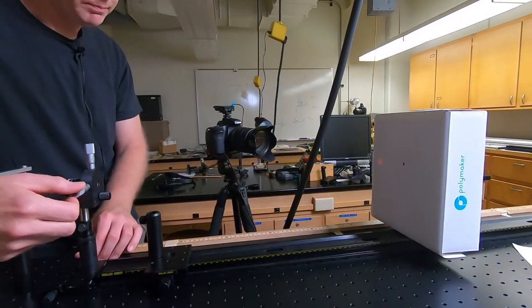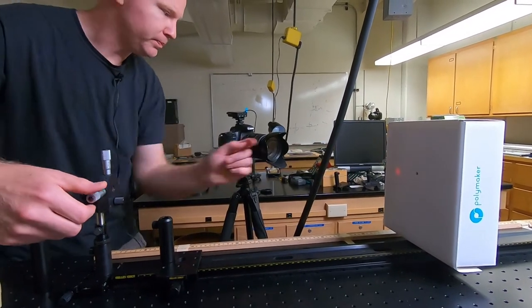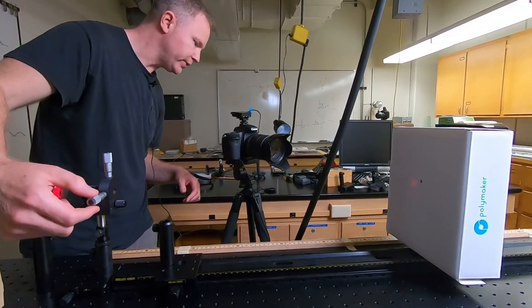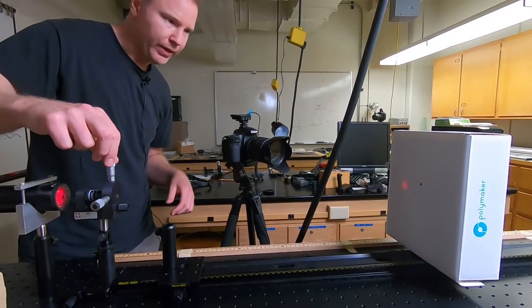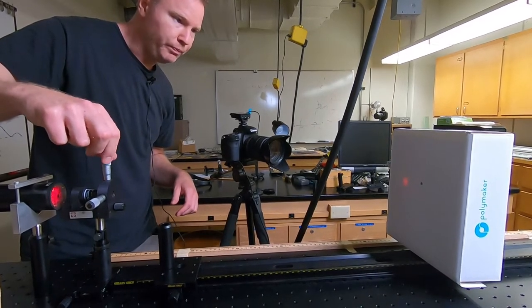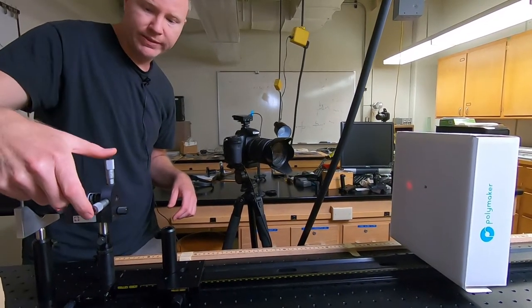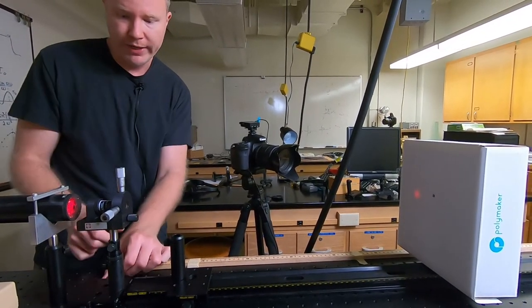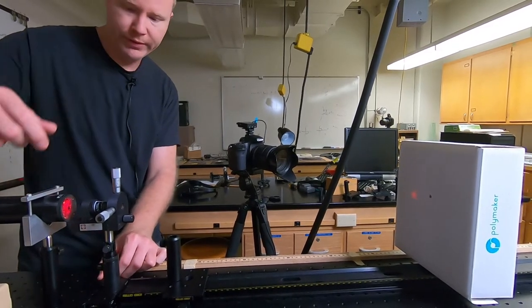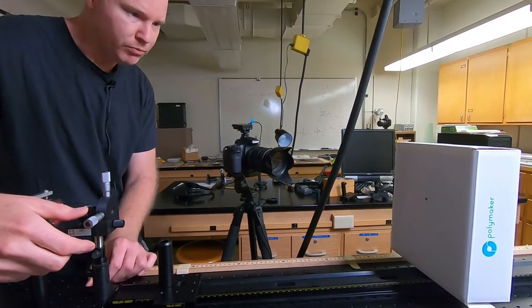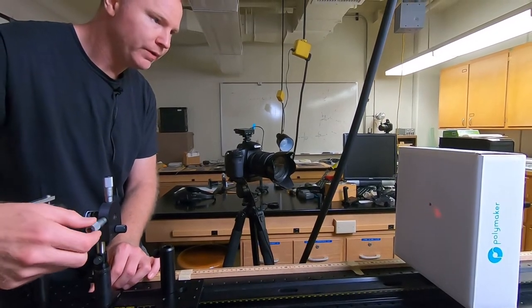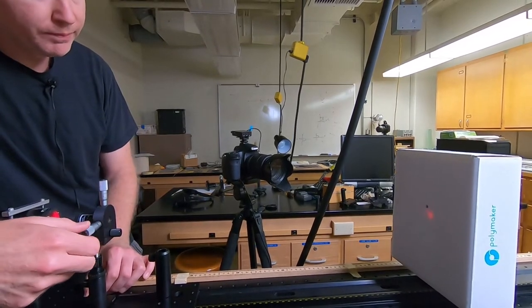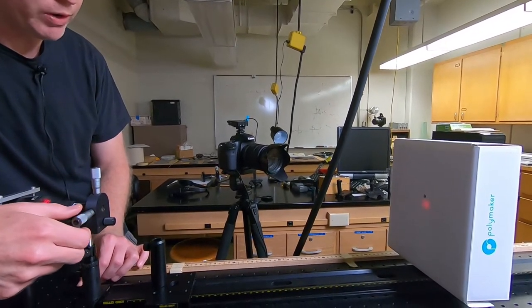The X and Y adjustment, I want to adjust it to make this spot as bright as possible. On the zoom in camera you can sort of see in the center where it's bright, and the Y adjustment, same thing. I'm not worrying about the position when I'm doing these X and Y adjustments of the pinhole. The position is determined by the overall X and Y adjustment of the whole mount. So if it's too far to the left, which it is, I need to move it over and then adjust the pinhole to match, adjust it so that the maximum brightness happens where I want it to happen.